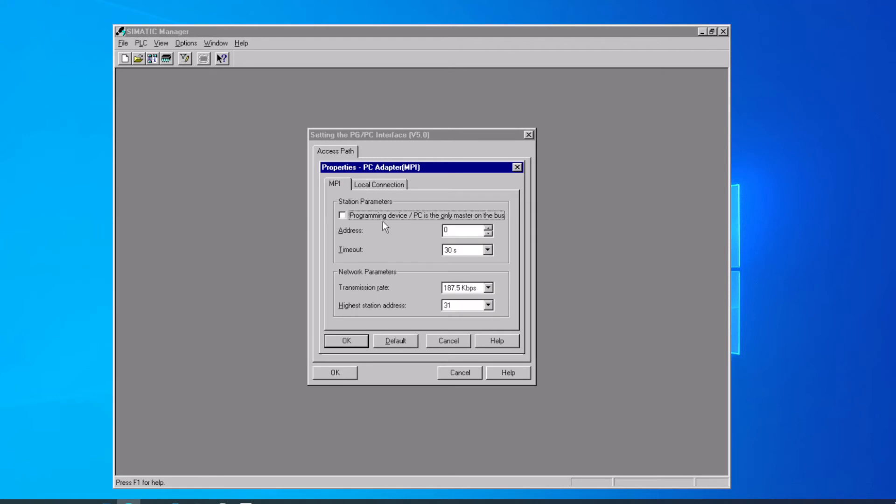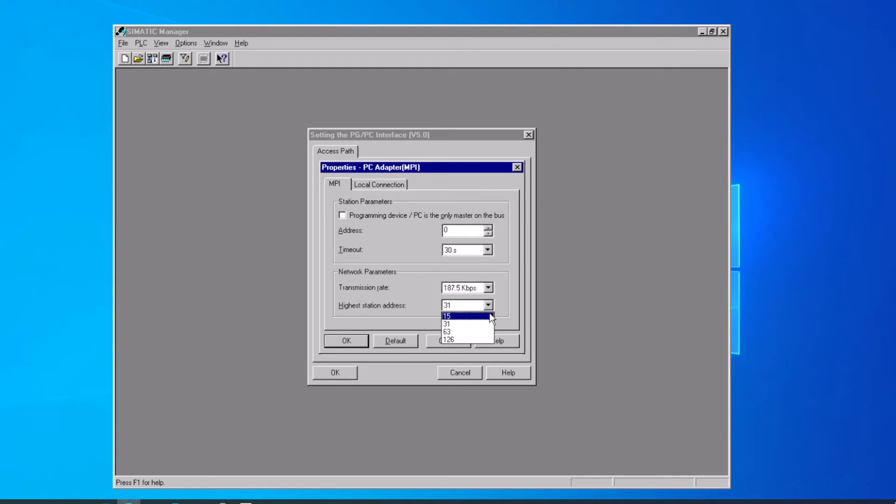On MPI, we also have the baud rate there at 187.5k baud, that's the standard rate. If you know you're not going to be talking to a large MPI network, you can save some time when you're looking for nodes on the network by setting that highest station address down to a number that's closer to what's actually on the network.